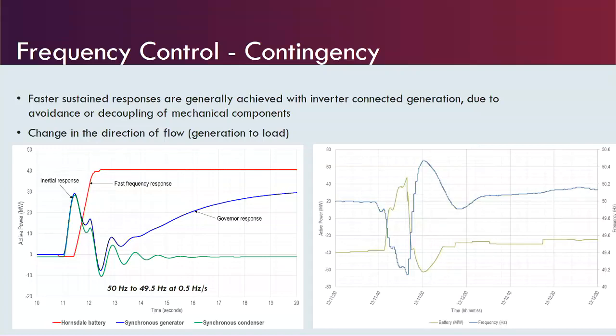Here we've got a beautiful response programmed in to be like a pseudo-governor, proportional to the frequency. What we find from batteries is that they can provide really good, really fast frequency response, both in the slower secondary control and the faster primary control.